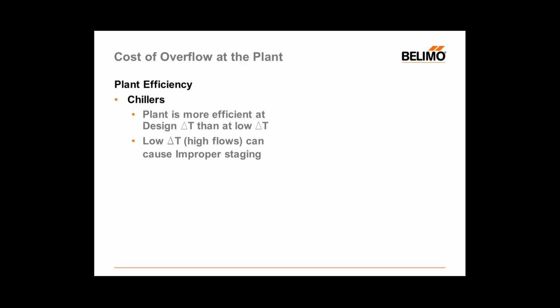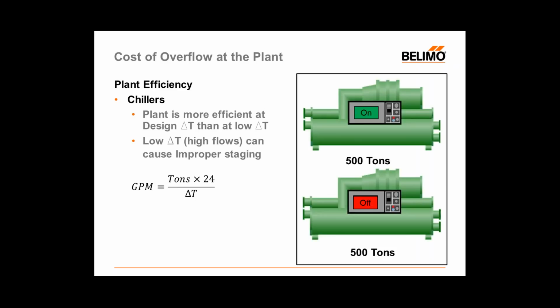The other thing that's more tangible, though, is that if we have low delta T, which will cause these high flows, it can cause my chiller to stage improperly, and we should go ahead and take a look at that, because this would be a little bit more universal if you're running a plant that has multiple chillers. Let's just say, as an example, we have 2 chillers, and they're 500 tons apiece, so I have a 1,000-ton capability on my plant. And we'll say right now that we have a 500-ton load. And so we would have one chiller loaded at 100% to get this 500 tons.